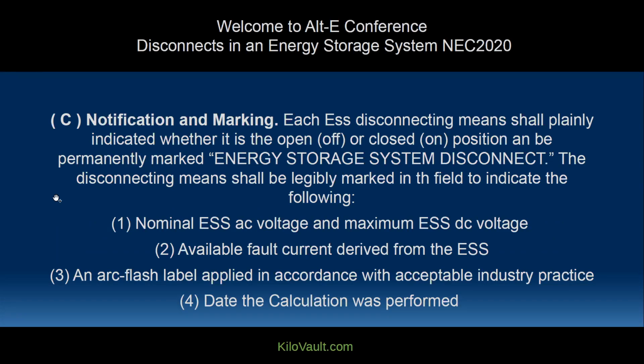Notification markers that are required for each ESS disconnect shall plainly indicate whether it is in the open, which is the off position, or closed, the on position, and be permanently marked "energy storage system disconnect." The disconnect means shall be legibly marked in the field to indicate the following: the nominal ESS AC voltage and maximum ESS DC voltage, available fault current derived from the ESS, an arc flash label applied in accordance with acceptable industry practices, and the date this calculation was performed.